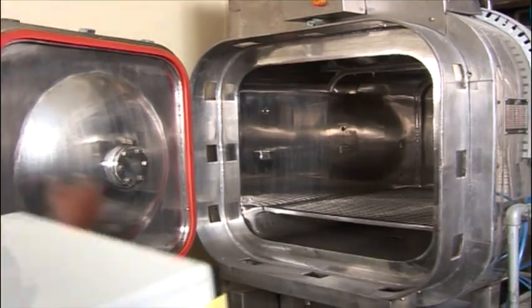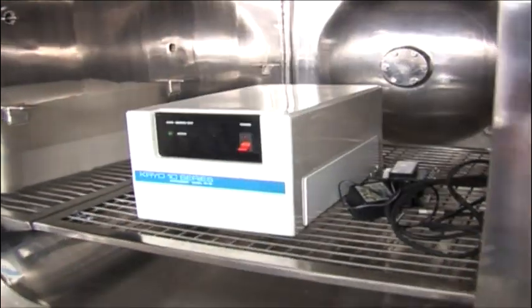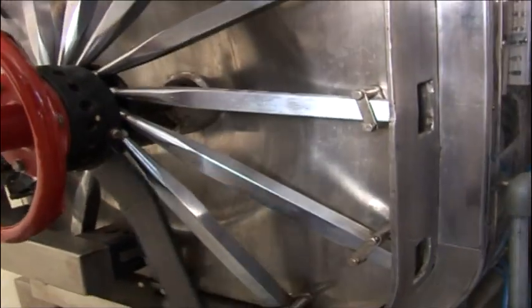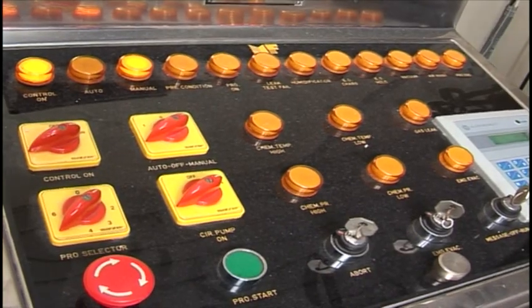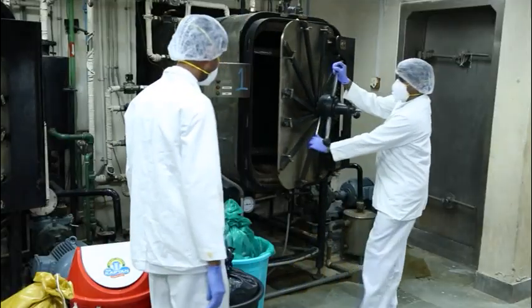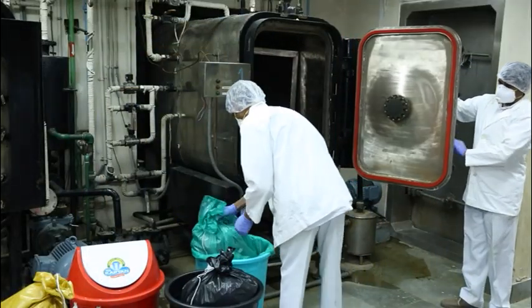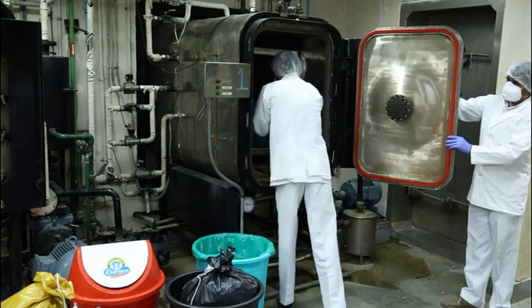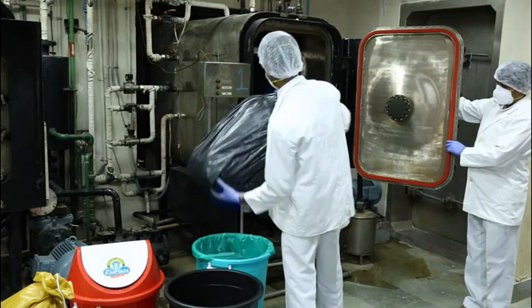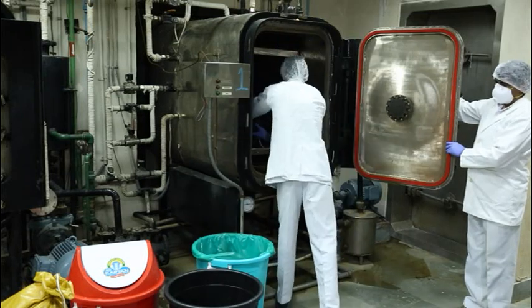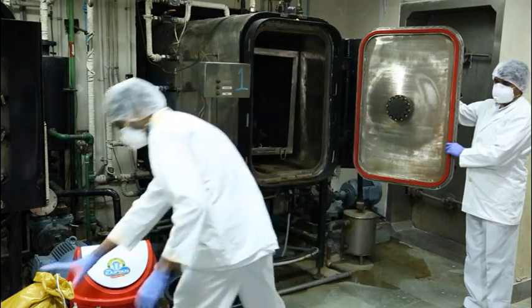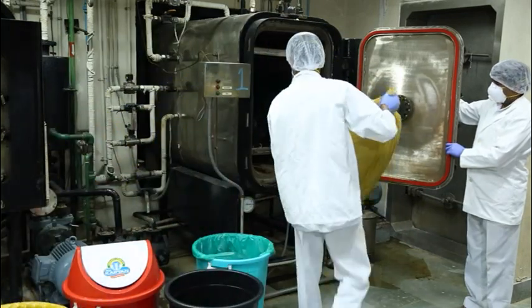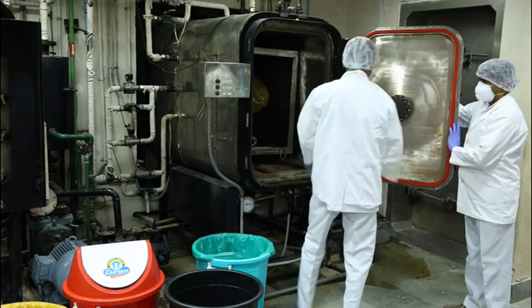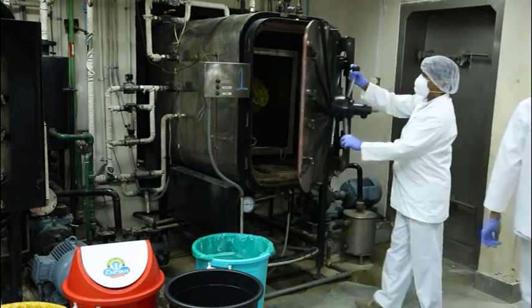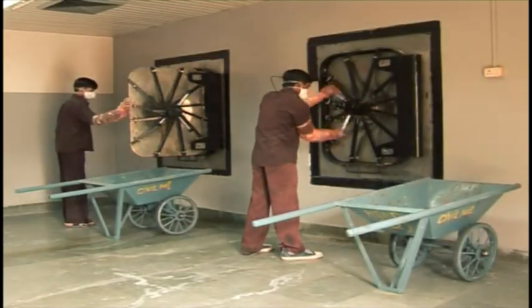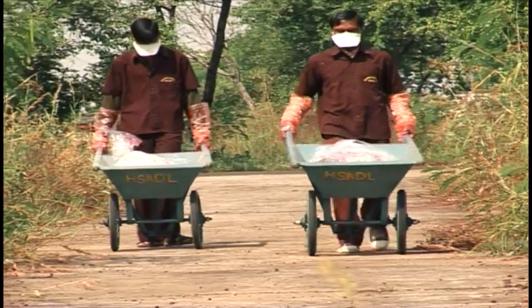All material that is sensitive to heat and chemical treatment is sent outside the lab through a double door barrier ethylene oxide gas sterilizer that opens outside the containment area. For discard of solid wastes, there are 2 double-door barrier autoclaves with ends opening inside and outside the containment area. The autoclaved hazardous waste material is sent further for incineration as per pollution control rules.